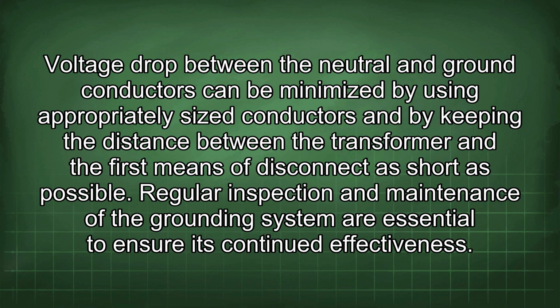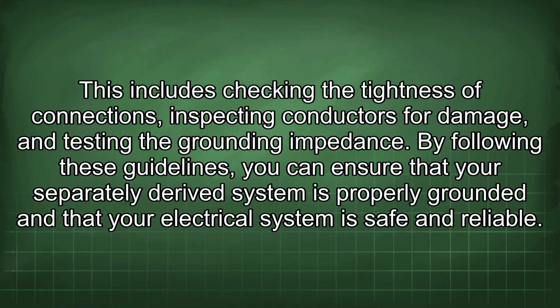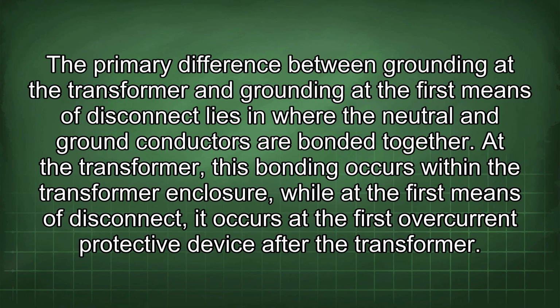Regular inspection and maintenance of the grounding system are essential to ensure its continued effectiveness. This includes checking the tightness of connections, inspecting conductors for damage, and testing the grounding impedance. By following these guidelines, you can ensure that your separately derived system is properly grounded and that your electrical system is safe and reliable.